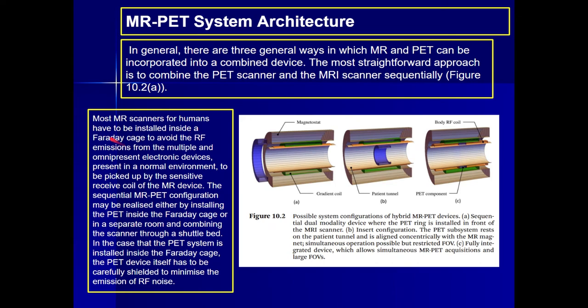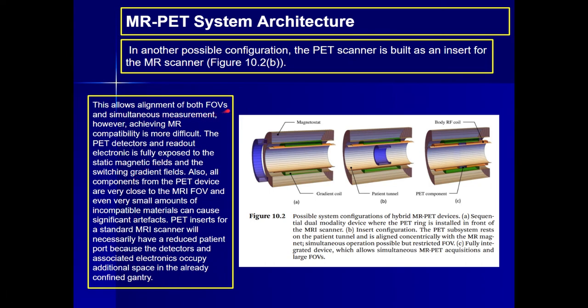Most MRI scanners for humans have to be installed inside the Faraday cage to avoid the RF emission from the multiple and omnipresent electronic devices present in a normal environment being picked up by the sensitive receiver coil of the MR device. The sequential MR PET configurations may be realized either by installing PET inside the Faraday cage, or in a separate room and combining the scanners through a shuttle bed. In the case that the PET system is installed inside the Faraday cage, the PET device itself has to be carefully shielded to minimize the emission of RF noise. This allows alignment of both FOVs and simultaneous measurement.